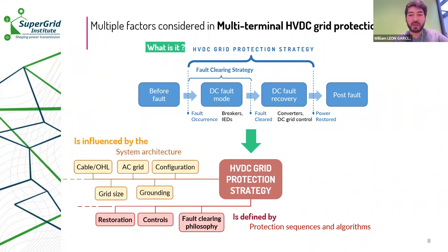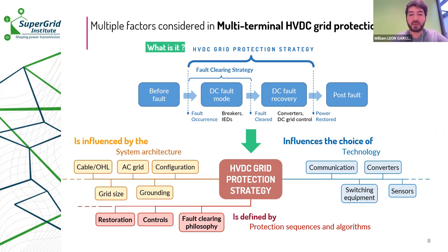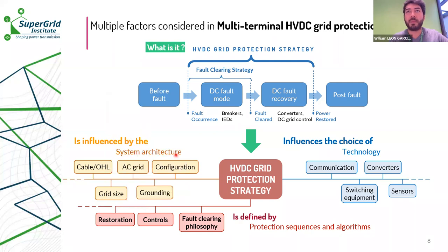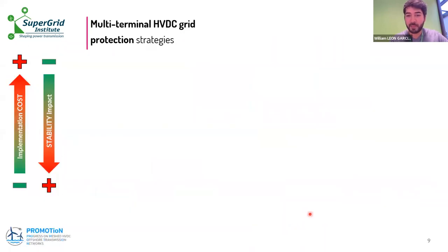The MTDC protection strategy can be influenced by various factors such as system architecture, the presence of cables or overhead lines, the system grounding, the MTDC grid size, and more. The choice of a protection strategy also influences the choice of certain technologies such as sensors, switching equipment, and communications. We've participated in protection projects since 2016 and came up with three categories of protection strategies.